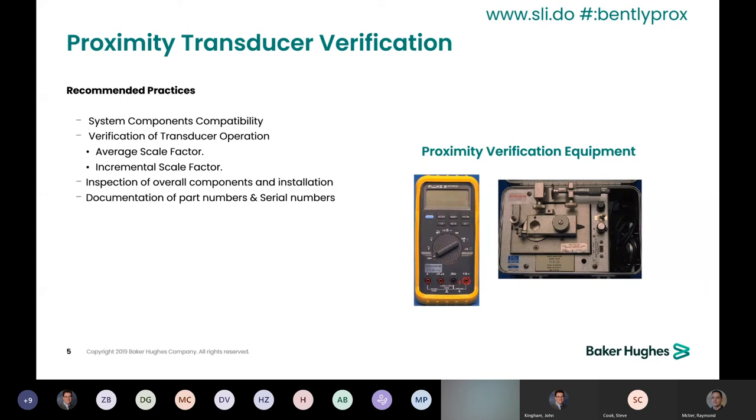The TK3 also has a spindle micrometer mounted at the top of the unit. This micrometer lets you make precise adjustments in the distance between the target of the micrometer and the tip of the probe. You create a verification curve by setting the micrometer to precise gap intervals and then recording the corresponding DC voltage as displayed on the DVM.